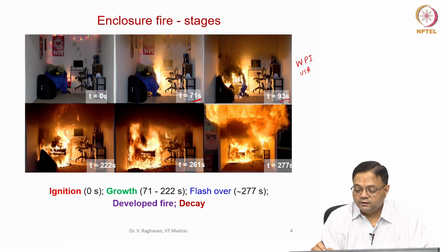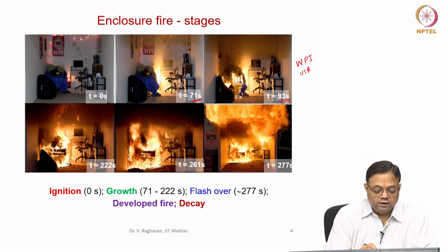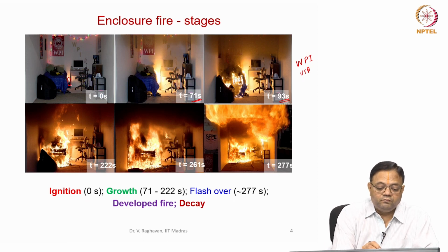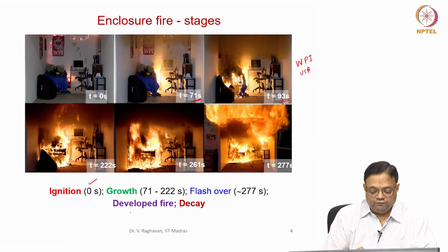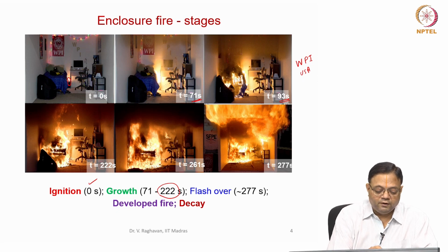Once you go to about 93 seconds, you see that the other commodities also are ignited, and the bed is in fire basically. So ignition, where a sustained flame is observed, is the time t equal to 0.